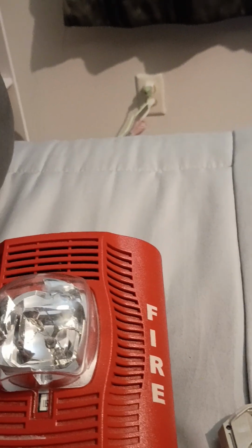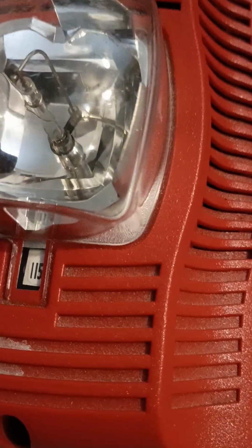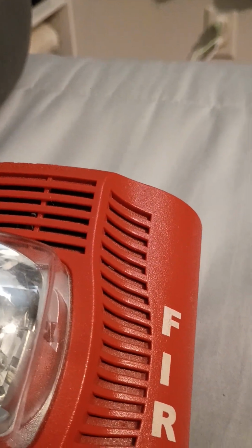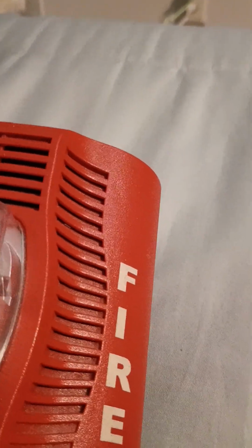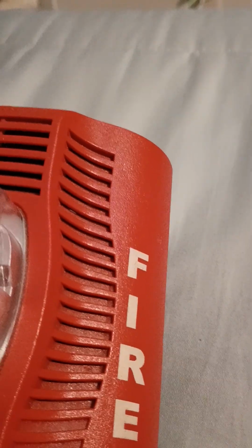And NFPA 70 would be the National Electrical Code. NFPA 72 would be the National Signaling Code or something like that. It does have something to do with the notification devices. And for those of you that know, I know a lot about devices. NFPA 13 has a lot to do with sprinkler systems. And don't get confused, guys, with NFPA 13 and NFPA 25. NFPA 25 is the testing and operable functioning of the overhead sprinkler system, which is a suppression system for the overhead sprinklers. So NFPA 25 would be the operable overhead sprinkler system. So you'd test those. That would be tests. NFPA 13 is the installation of the overhead sprinklers.